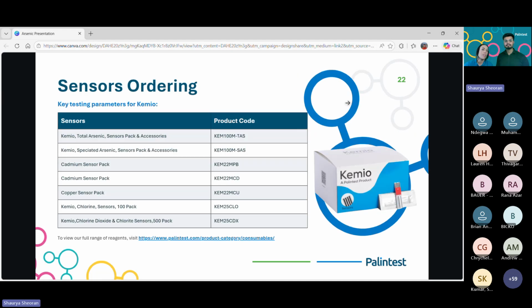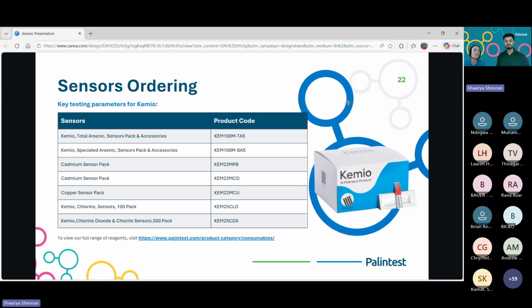So this just shows the heavy metals tests that are available, some of the different ones. You have arsenic, as we've covered today, cadmium, copper, and we have lead on the disinfection device, which would be on the Multi. So if you go for the Multi to get the metals and the disinfection, there are parameters such as chlorine dioxide, chlorine, peracetic acid.